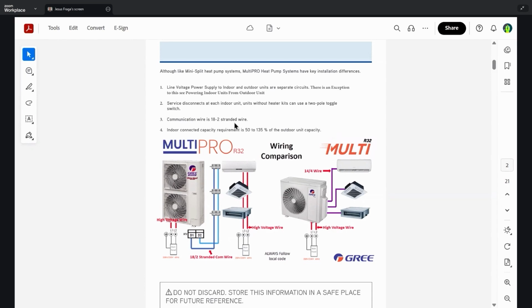The communication wire is 18/2 stranded wire. It does not have to be shielded, just stranded. And the indoor connected capacity requirement is the same as the 14A model, so you have to have a minimum of 50% and a maximum of 135%. If you fall out of that window, the unit will not start and will give you an error code. Depending on whether you're low or high will determine the error code that you see.